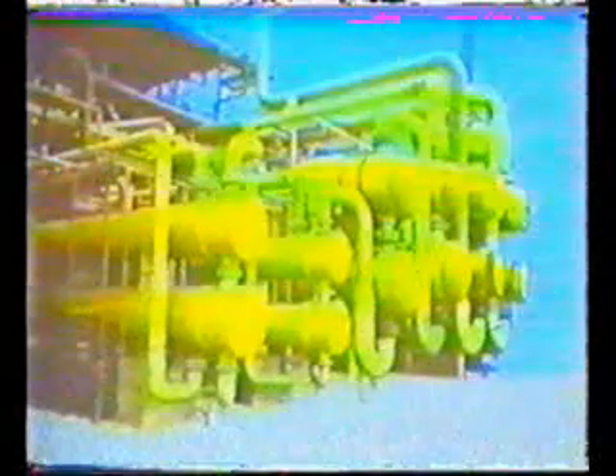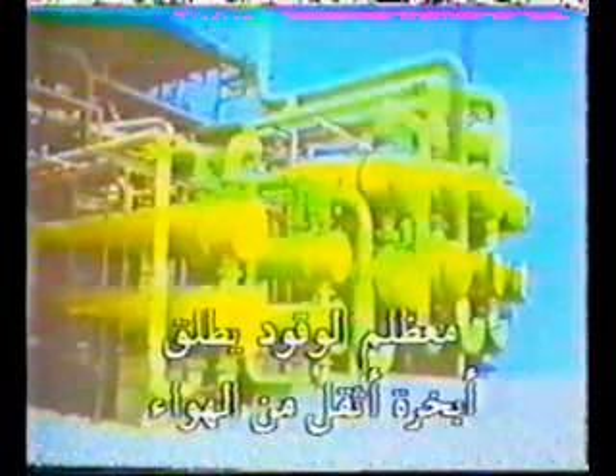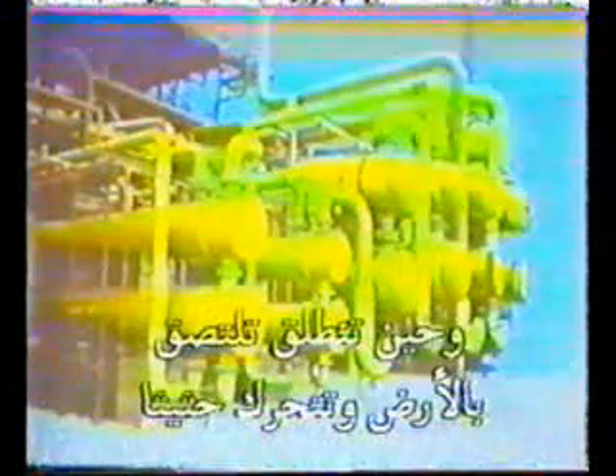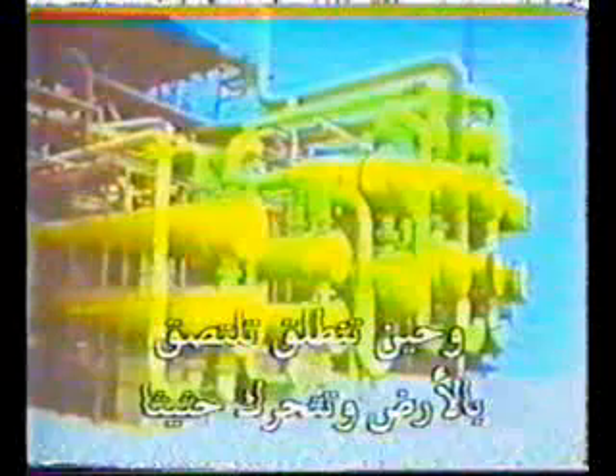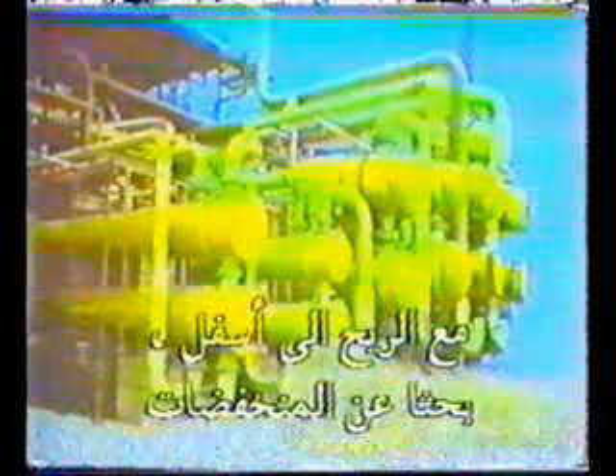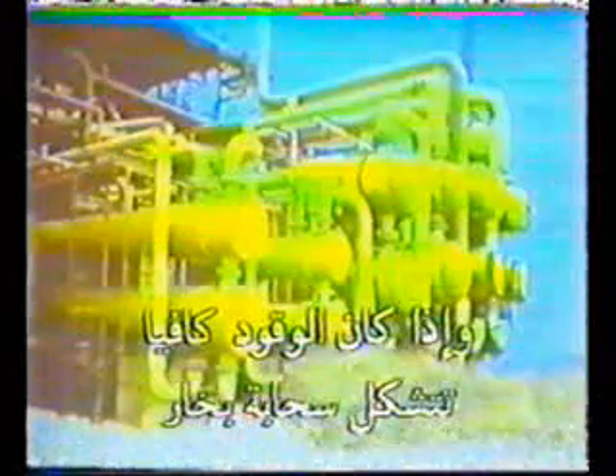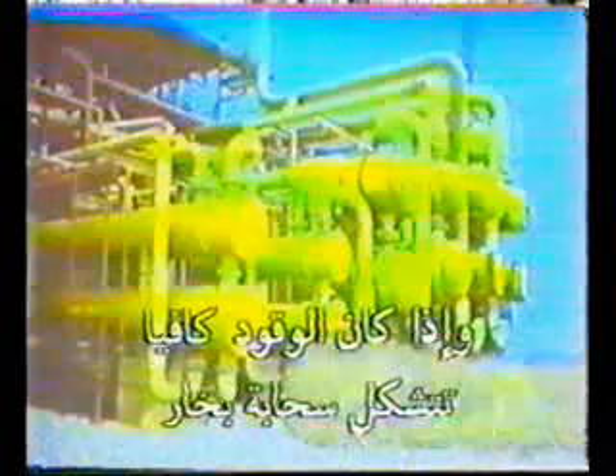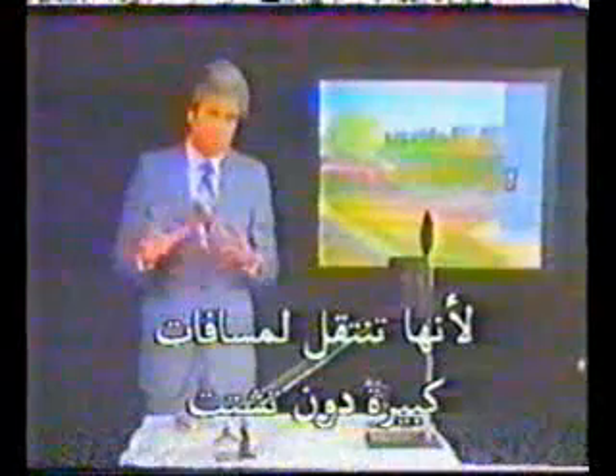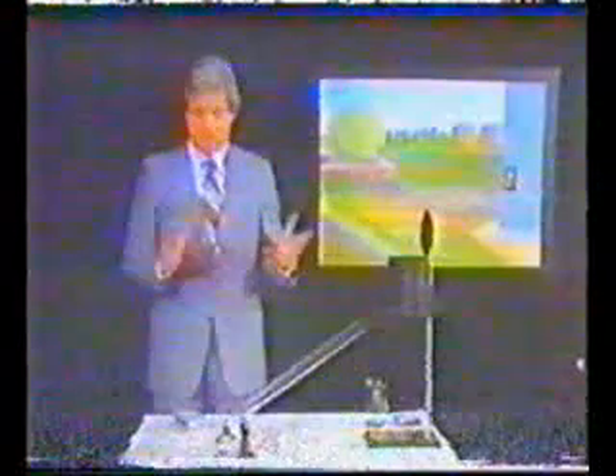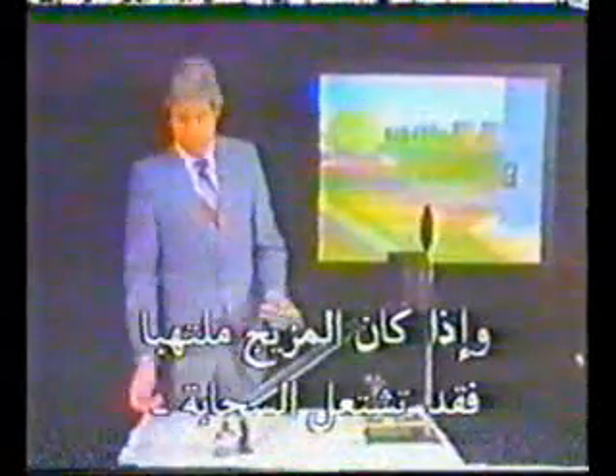Most fuels produce vapors that are heavier than air. When these types of vapors are released, they will tend to cling to the ground and gradually move downwind and downhill, seeking low areas. If enough fuel is released, a vapor cloud may be formed. Vapor clouds are extremely dangerous because they can travel a considerable distance without being dispersed. If a flammable mixture is present, the cloud may be ignited by any nearby source of ignition.